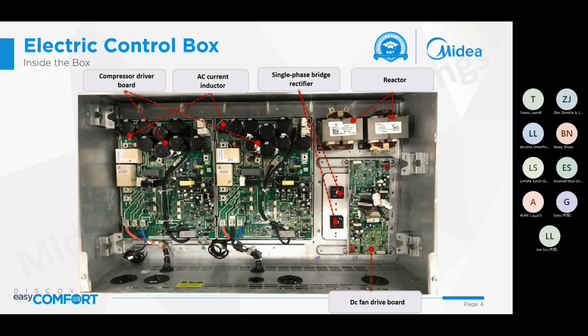In the right down corner is the DC fan drive board. We can also see two DC fan drive boards, for driving the DC fan motors, each drive board for one DC fan motor. Inside the control box there are two layers. The outside layer has the main PCB, and the inside layer has the compressor drive boards and DC fan drive boards.